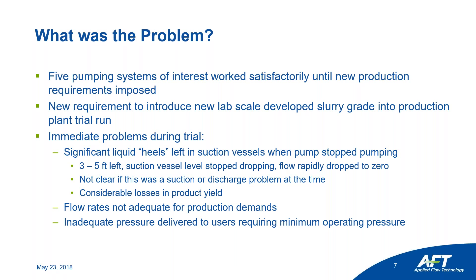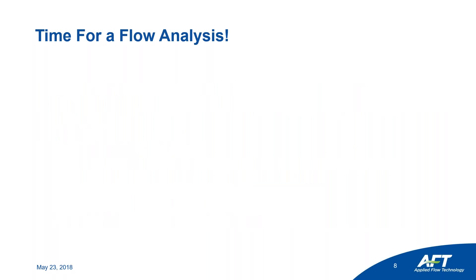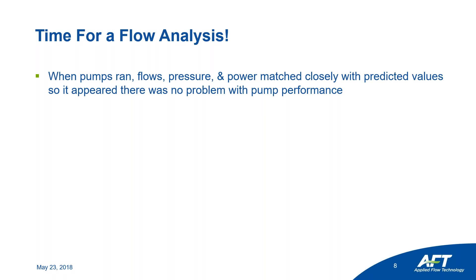Additionally, they did not ensure enough pressure delivery to various areas of their system that required a minimum operating pressure. It was time for a flow analysis. When the pumps ran, their flows, pressures, and power data matched the model's predicted values very well for their original lab-scale cases, so there was no problem with the pump performance itself.